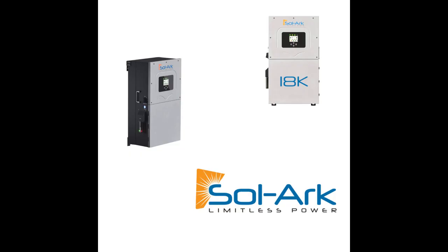Thanks, Mark. Yeah, we've already touched again on the specs, like Mark said. One of the things I want to highlight here is, some people will ask, what is the difference? You say usable PV power, right? What does that mean? Because our spec sheet clearly says 18K. So basically, all we're trying to highlight here is that while doing 18 kilowatts to your load, you can also do that additional difference, up to 28 kilowatts straight from the PV array to the battery. So that's that bonus power that would ordinarily be unused. You could just still pump that power into the battery. So really a big feature. We highlighted that on our 12K when we first released that, and then we're bringing that feature back here on the 18K. Very useful.